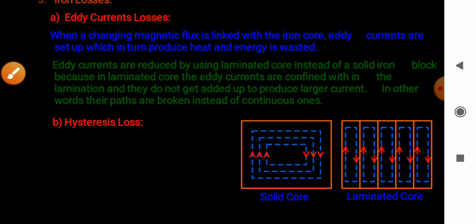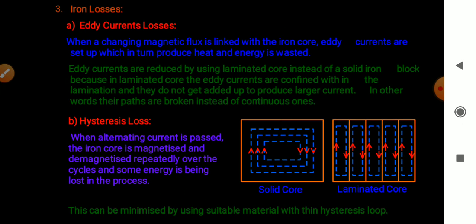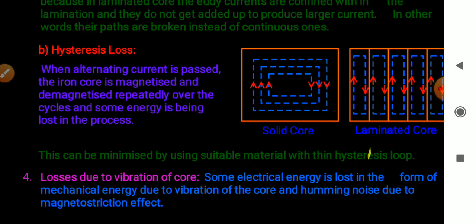The next iron loss is hysteresis loss. When alternating current is passed, the iron core is magnetized and demagnetized repeatedly over each cycle, and some energy is lost in this process. This can be minimized by using suitable material with thin hysteresis curves. Additionally, some electrical energy is lost in the form of mechanical energy due to vibration of the core and humming noise due to the magnetostriction effect.